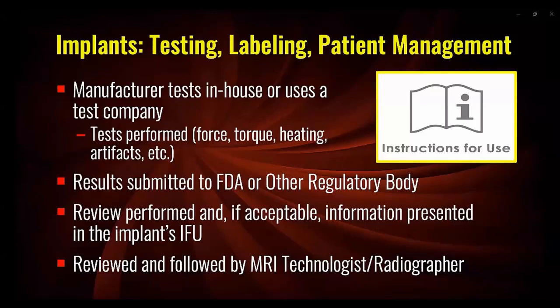And to my knowledge, with the exception of a few cochlear implants, there are no implants that have been specifically tested and labeled below a field strength of 1.5 Tesla. As such, there is a general lack of labeling information for low field strength MR systems.